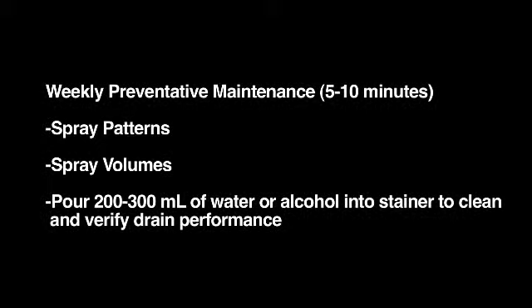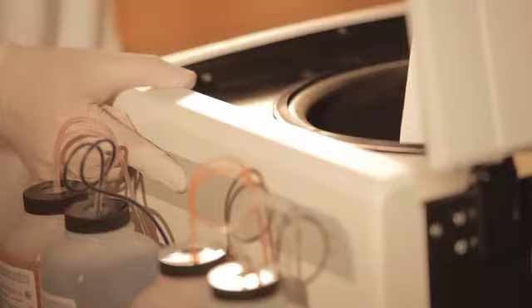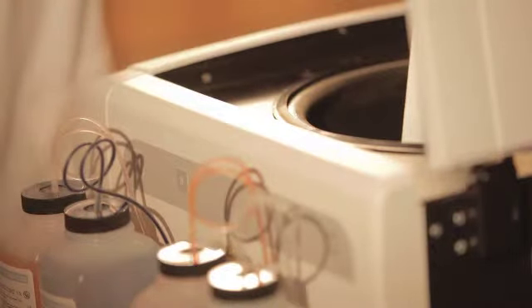Weekly preventive maintenance focuses on nozzle and drain performance. It should take 5 to 10 minutes. Good nozzle spray patterns and volumes are essential to proper staining. Users should check the nozzle performance by first checking the spray patterns and second checking the spray volumes. Checking the spray patterns is done by pressing Maint, then Option 1 for pattern test. The display indicates to press any prime button for a pattern test. Hold a paper towel against the hub of the stainer in front of the nozzle to spray.